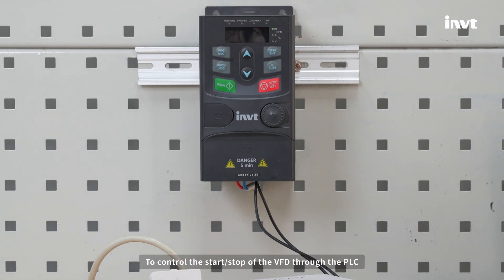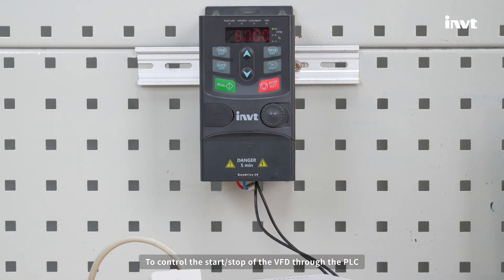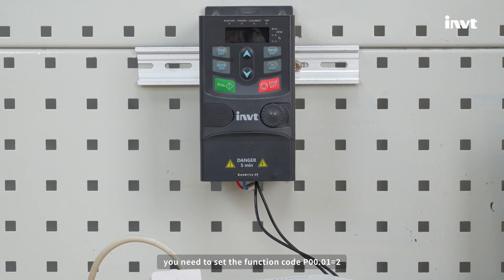To control the start or stop of the VFD through the PLC, you need to set the function code P00.01 equals 2.